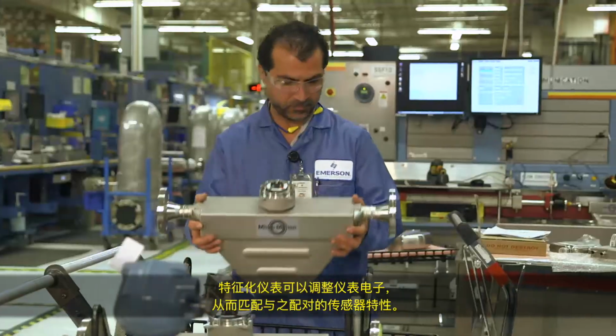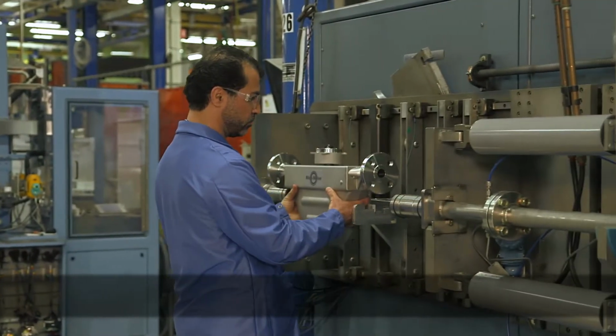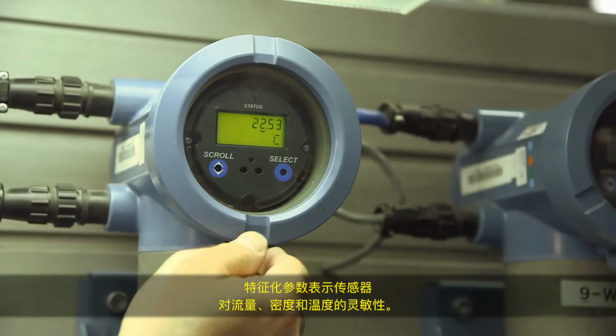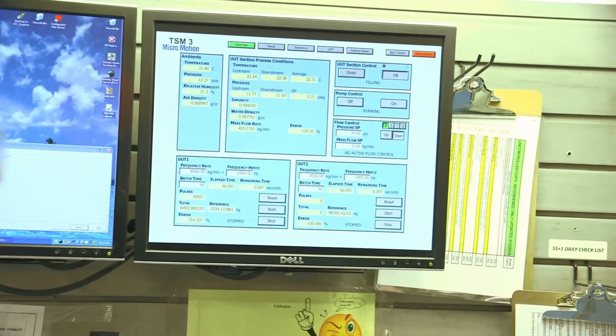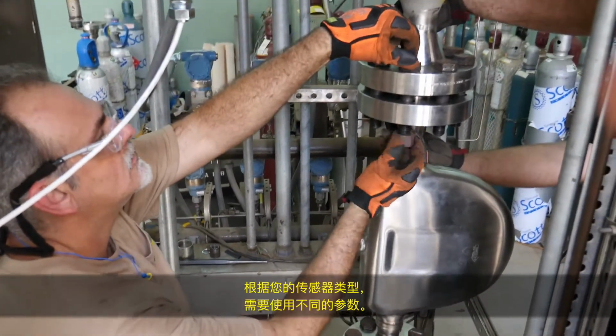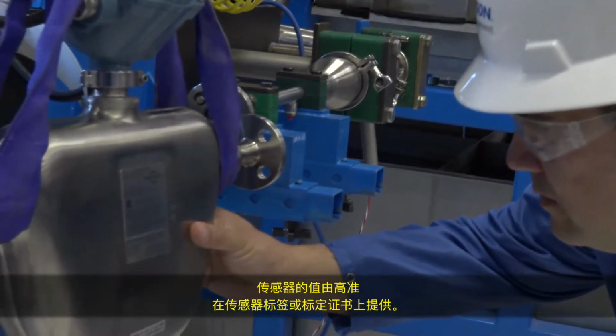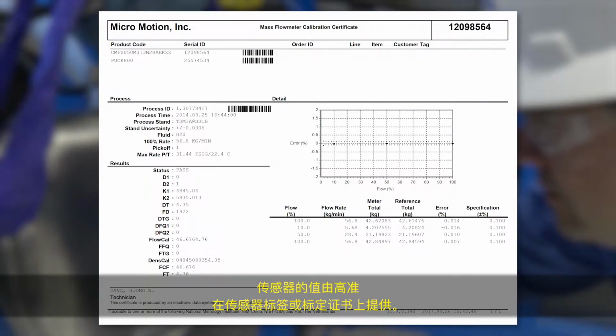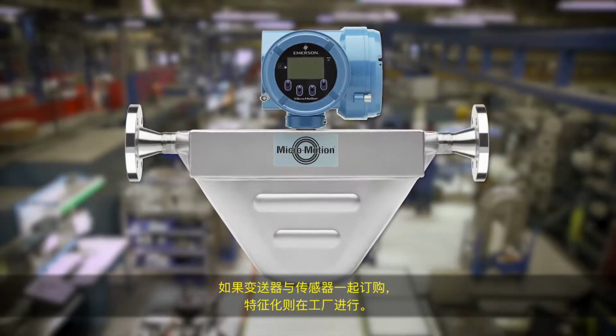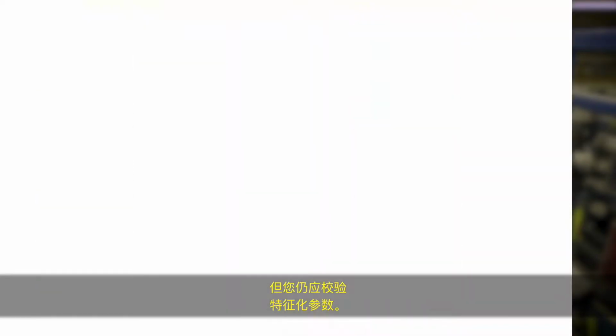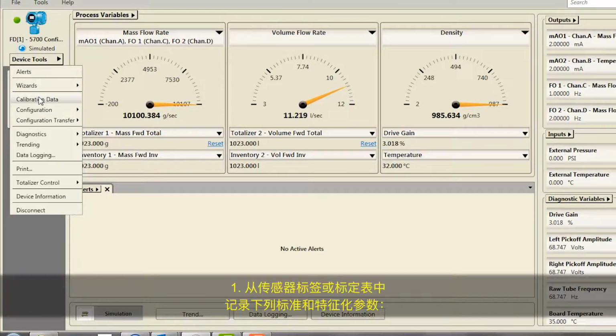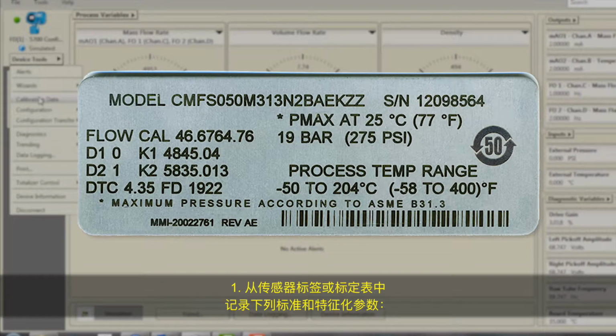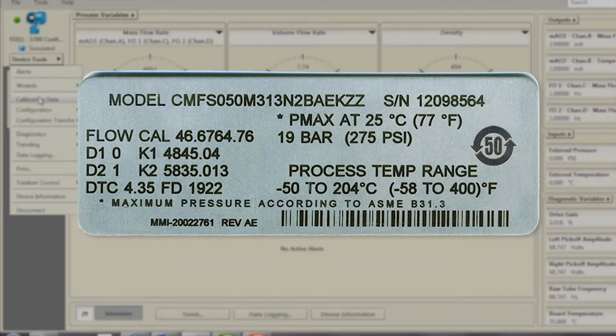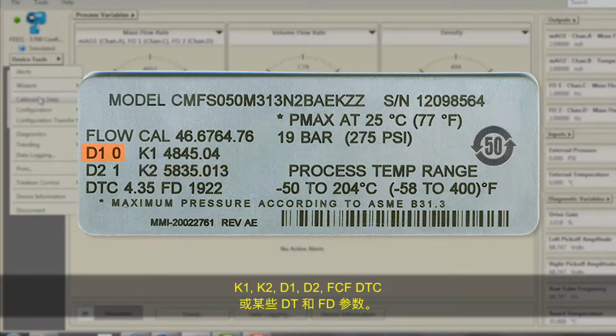Characterizing the meter adjusts the meter electronics to match the unique traits of the sensor it is paired with. The characterization parameters describe the sensor's sensitivity to flow, density, and temperature. Depending on your sensor type, different parameters are required. Values for your sensor are provided by MicroMotion on the sensor tag or the calibration certificate. If your transmitter was ordered with a sensor, it was characterized at the factory. However, you should still verify the characterization parameters. First, record the following calibration and characterization parameters from the sensor tag or calibration sheet: K1, K2, D1, D2, FCF, DTC, or sometimes labeled as DT, and FD.